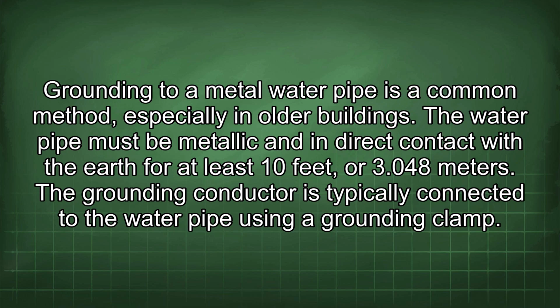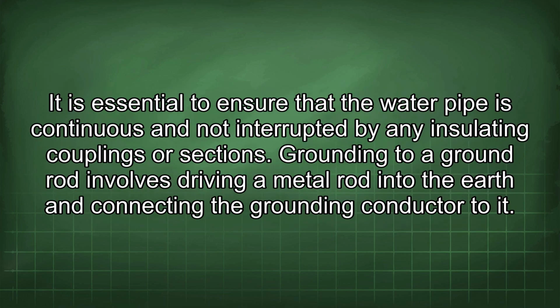The water pipe must be metallic and in direct contact with the earth for at least 10 feet, or 3.048 meters. The grounding conductor is typically connected to the water pipe using a grounding clamp. It is essential to ensure that the water pipe is continuous and not interrupted by any insulating couplings or sections.